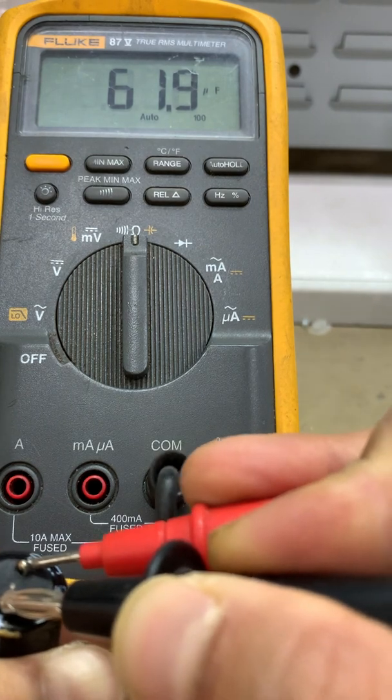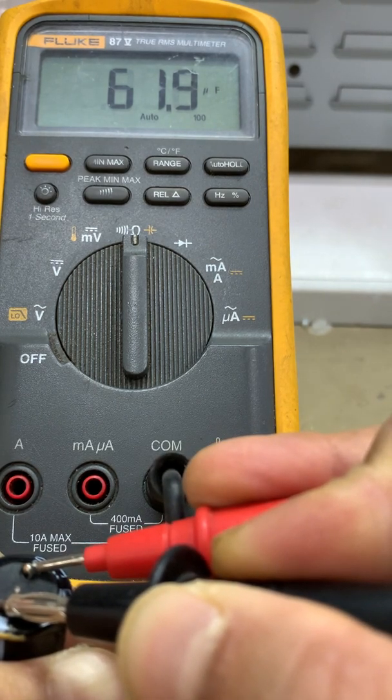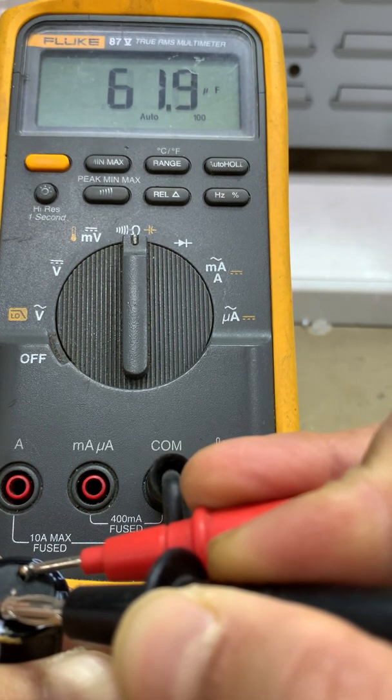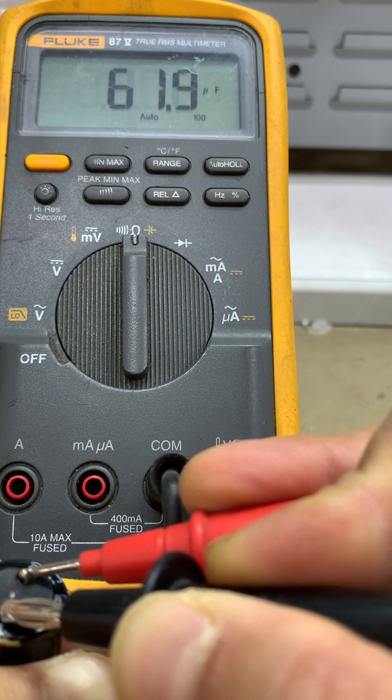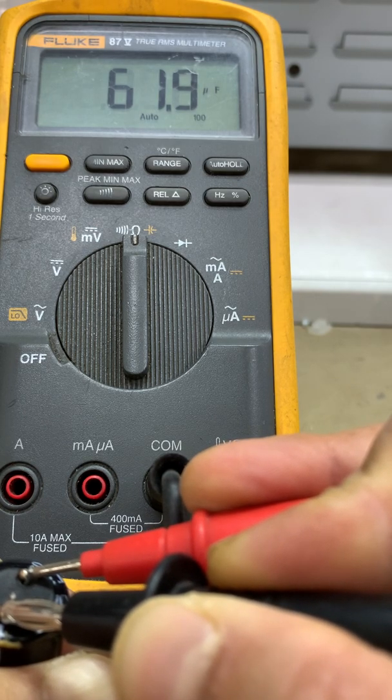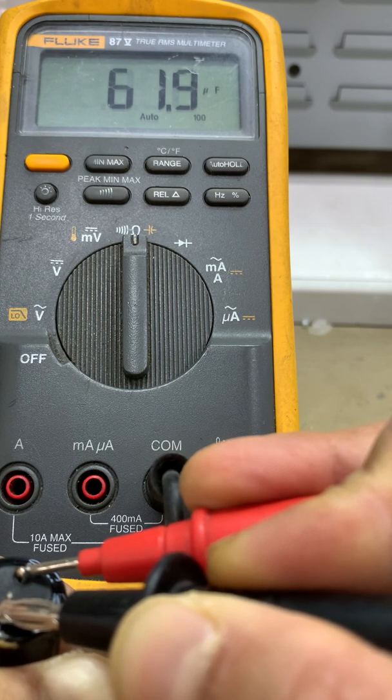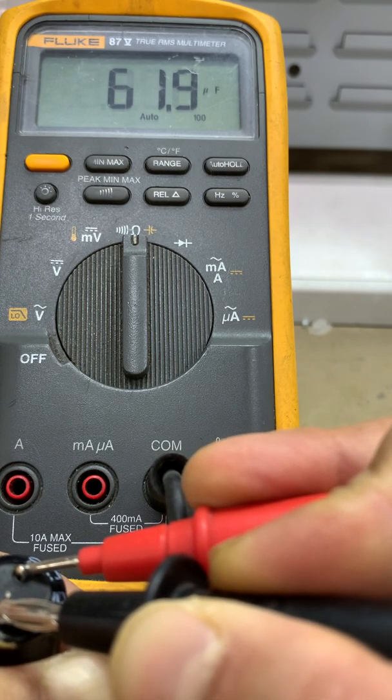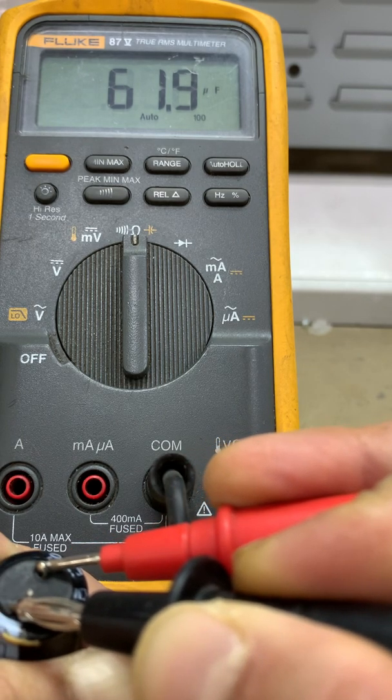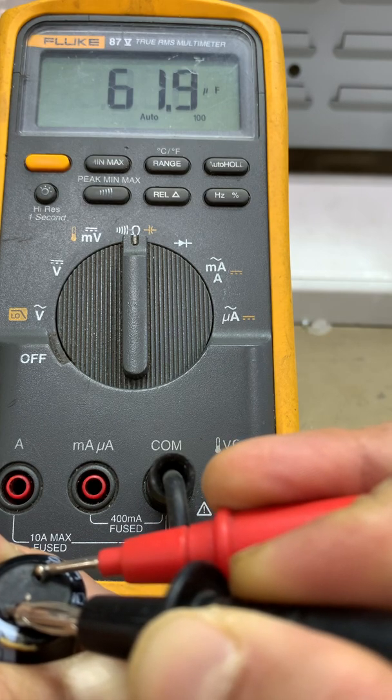As we can see, the value and reading is stable: 61.9, and the unit is microfarad. So this is the correct reading of the capacitor, 61.9 microfarad. It's steady, stable, and almost accurate.